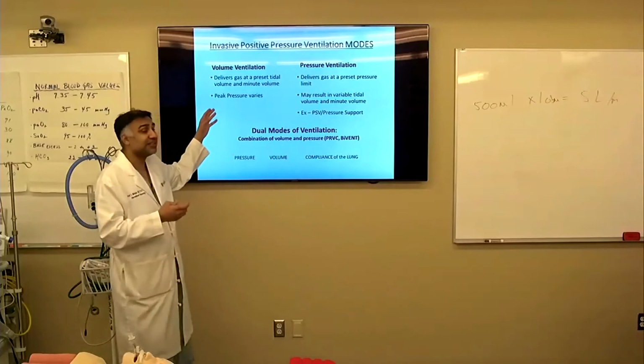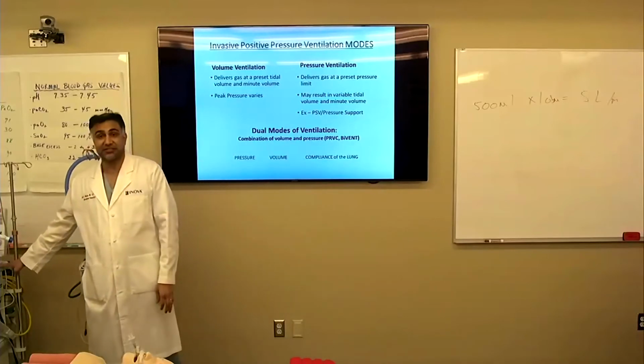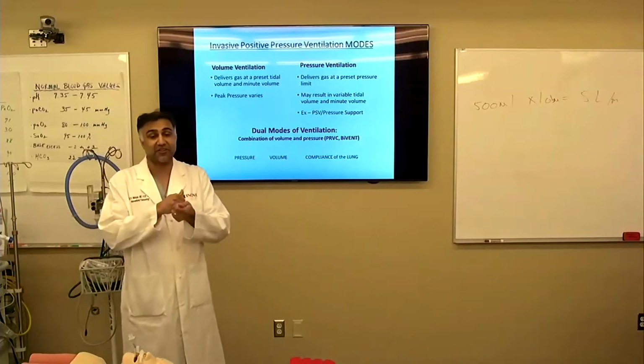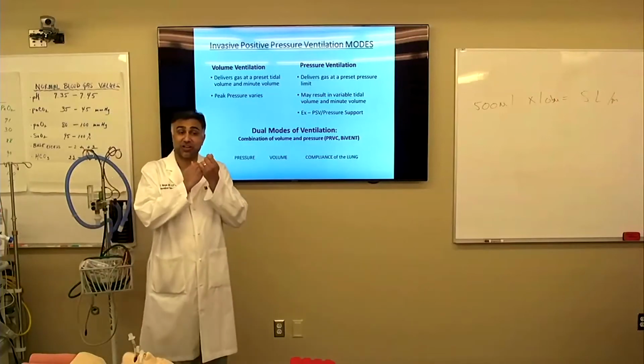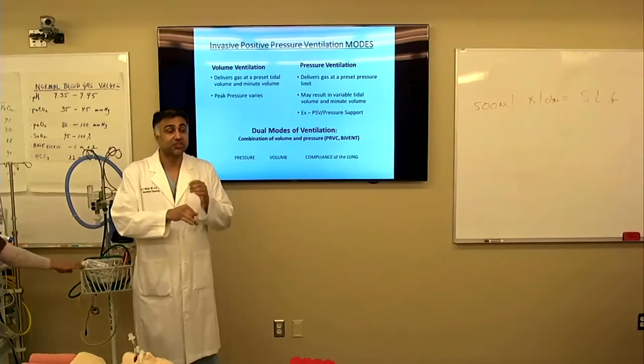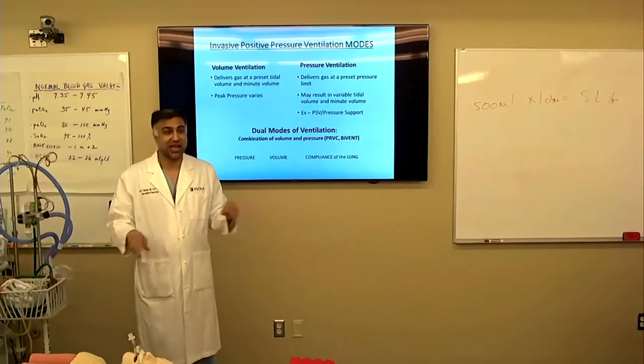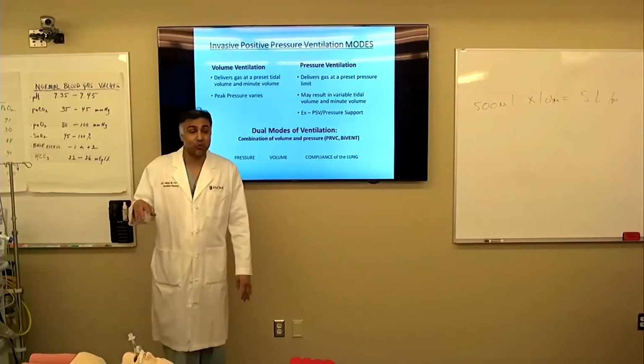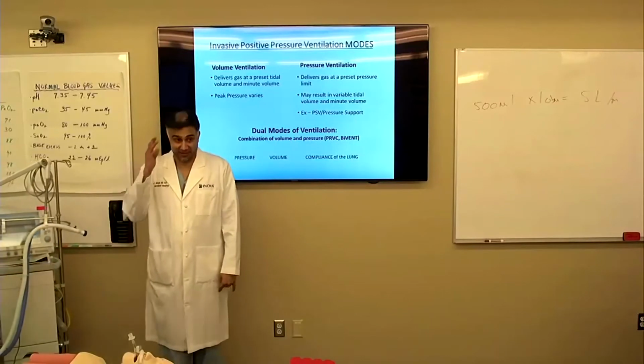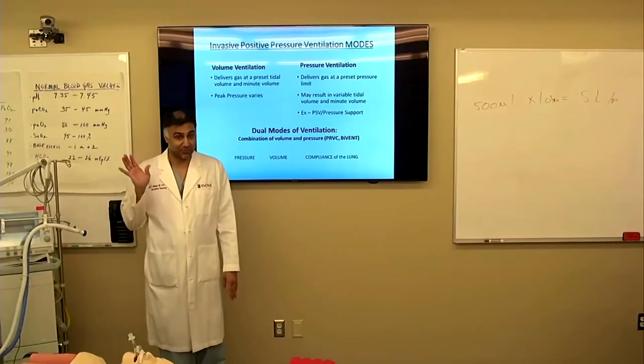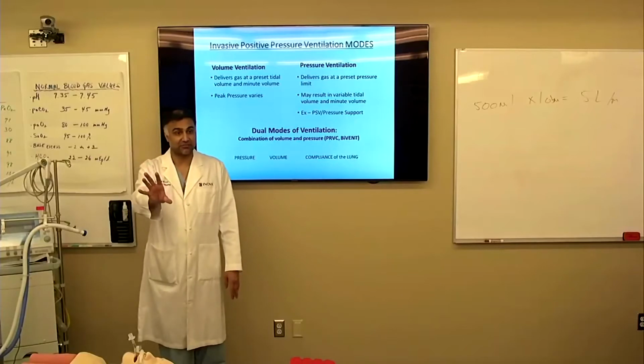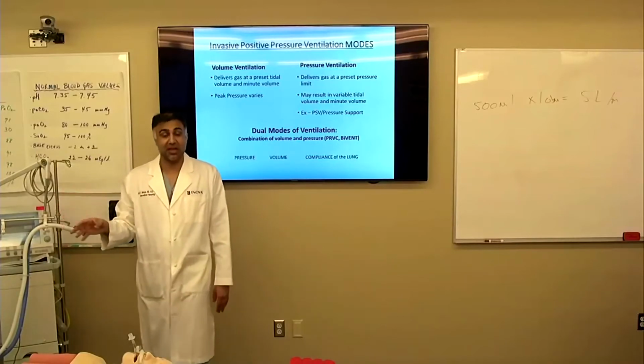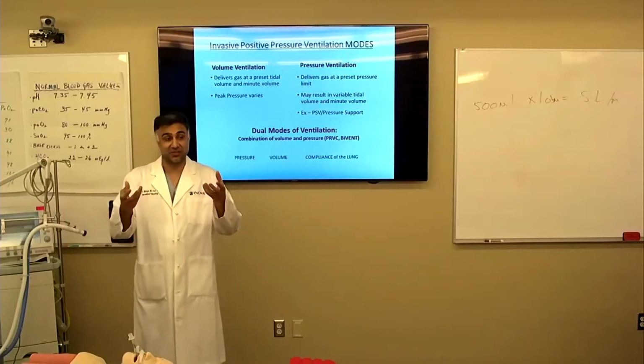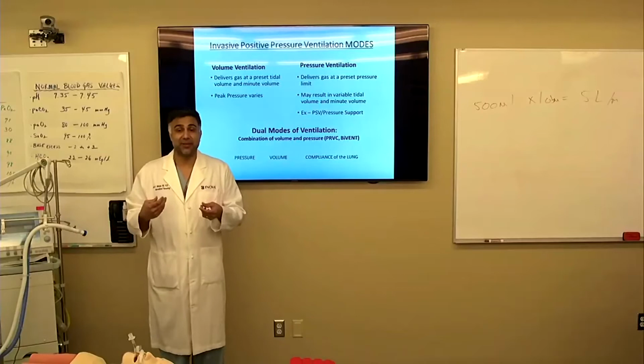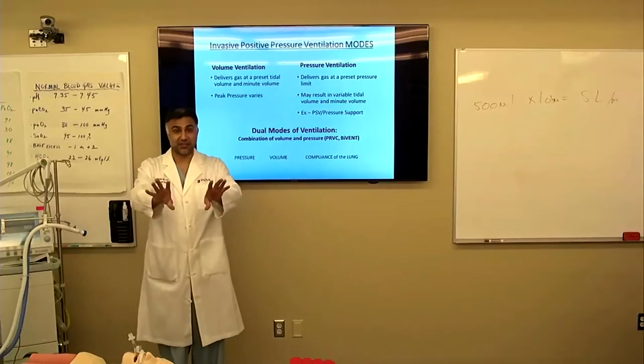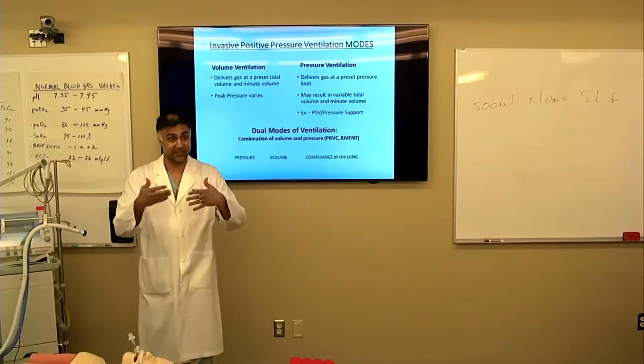So essentially, every time we put a volume into this ventilator, we say we're going to do 500 mLs for every breath, and we're going to do 12 breaths per minute, okay? So if we completely paralyze the patient and didn't let them breathe at all, every 5 seconds it would push in 500 mLs of air. They wouldn't do any kind of triggering at all. But the ventilator senses the patient trying to breathe. So every time the patient takes a breath, it senses that and pushes the air in, because it's trying to be synchronous with the patient. It's trying to give a breath to the patient when they want it.